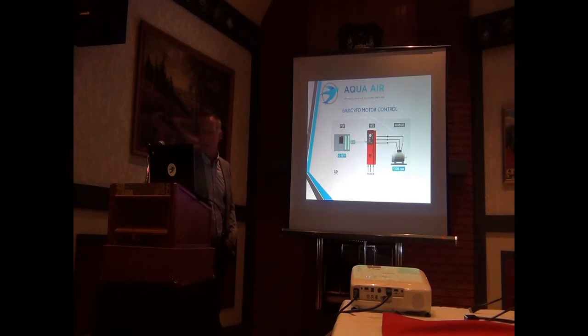And how does it work? You have a building management system here that sends out a 0 to 10 volt signal to the VFD. The VFD is programmed to interpret that signal. You can decide what that means, but in this case, it's interpreting the 5 volt signal to be 1750 RPM. So what it does, it interprets that and sends out, if this was a 60 hertz motor, 30 hertz to that motor.